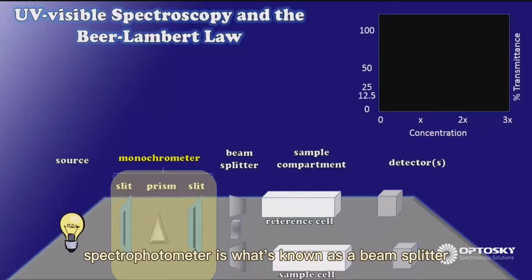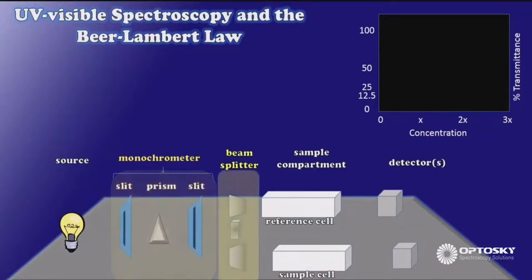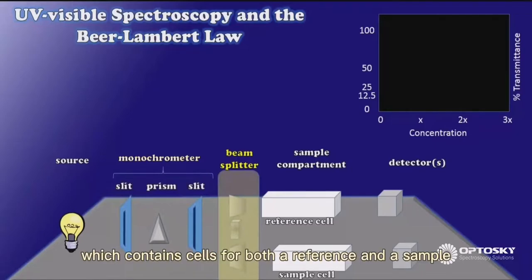The next element of our spectrophotometer is what's known as a beam splitter, which divides a beam of light into two equal parallel beams of light. Next is the sample compartment, which contains cells for both a reference and a sample.